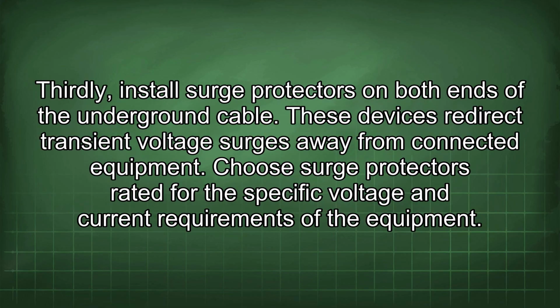Thirdly, install surge protectors on both ends of the underground cable. These devices redirect transient voltage surges away from connected equipment. Choose surge protectors rated for the specific voltage and current requirements of the equipment.